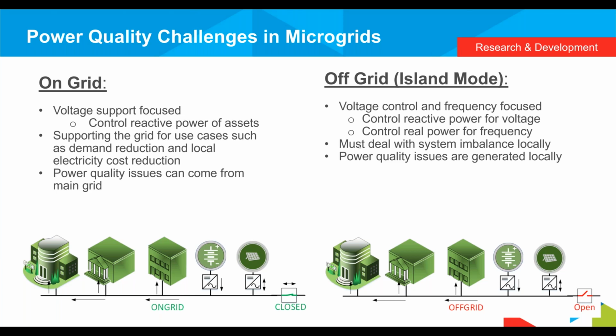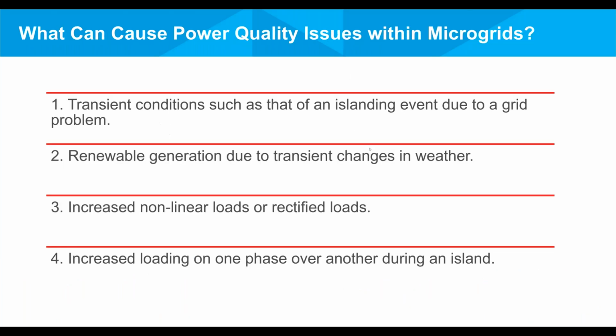And furthermore, the microgrid has to be able to deal with system imbalance locally, and finally, power quality issues that are generated locally. So these are things that one needs to consider in designing the control system for the microgrid. Now, what can cause power quality issues within microgrids?